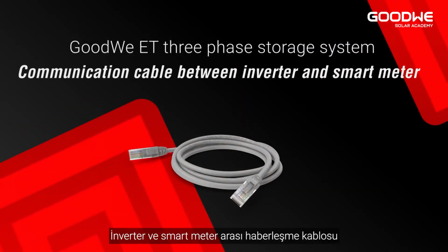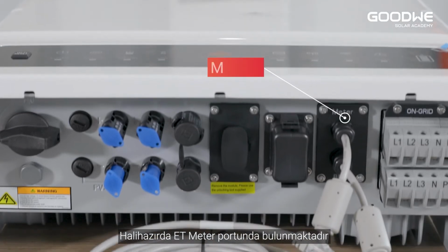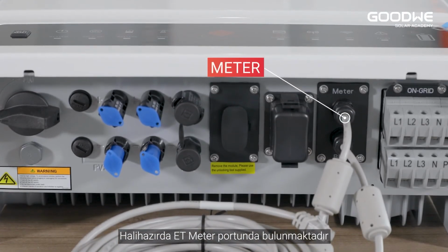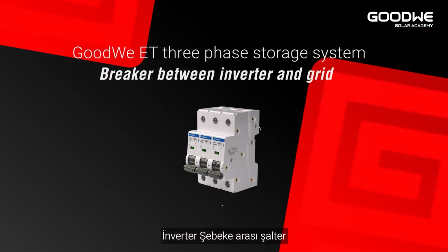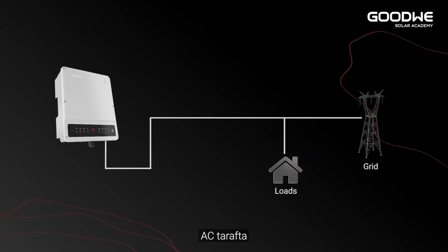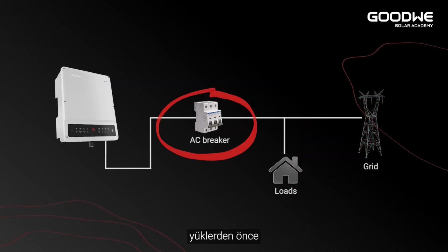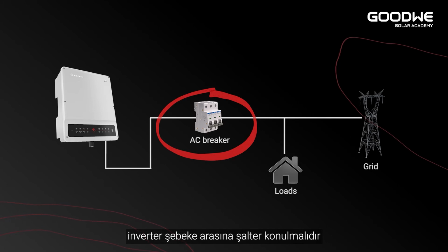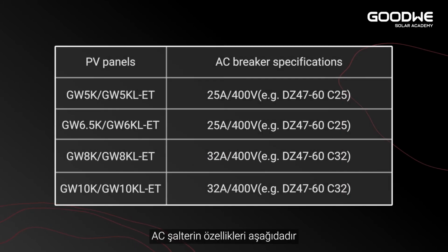Communication cable between inverter and smart meter. Integrated in the ET meter communication port. Breaker between inverter and grid. On the AC side, an individual breaker should be connected between the inverter and grid before any loads. The AC breaker specification suggestions are as below.